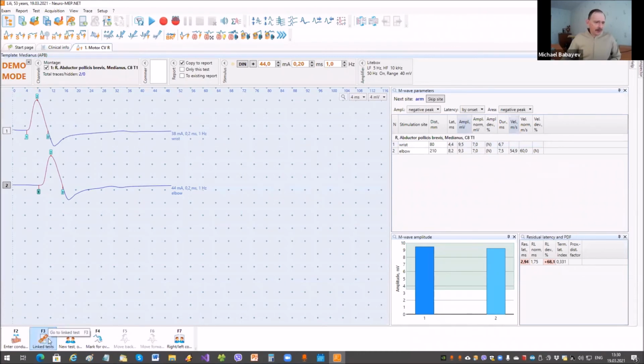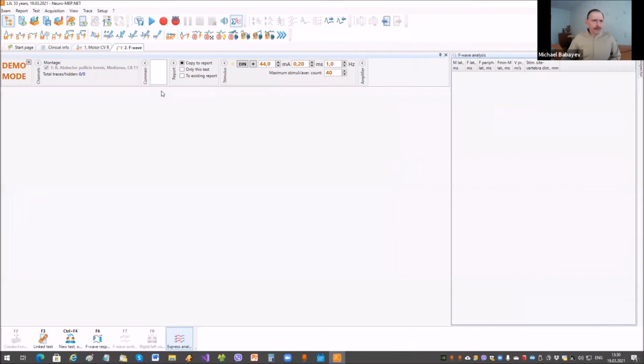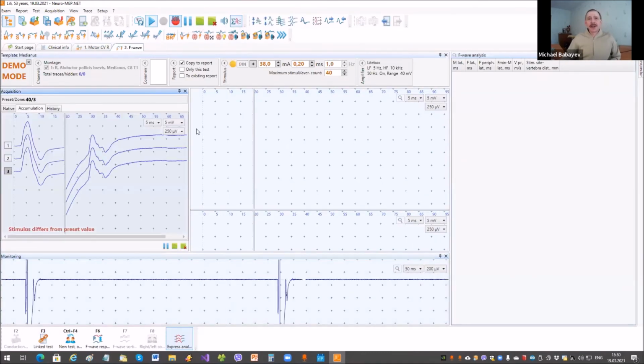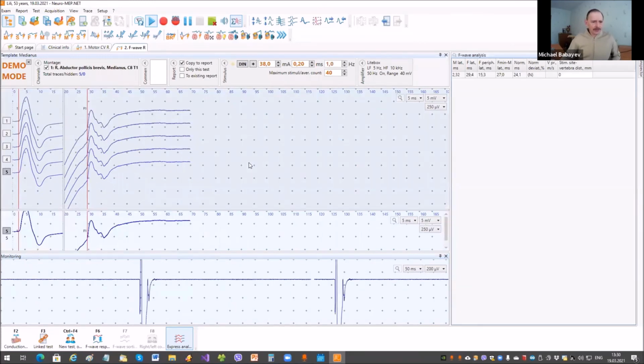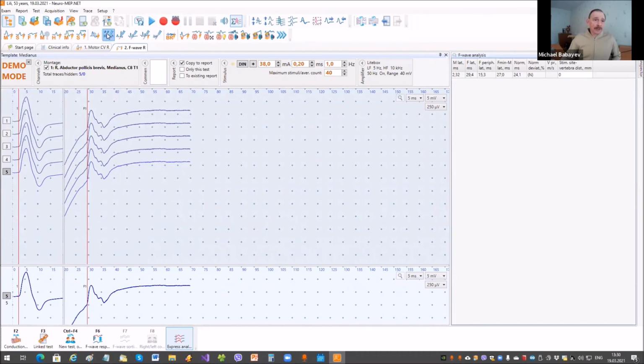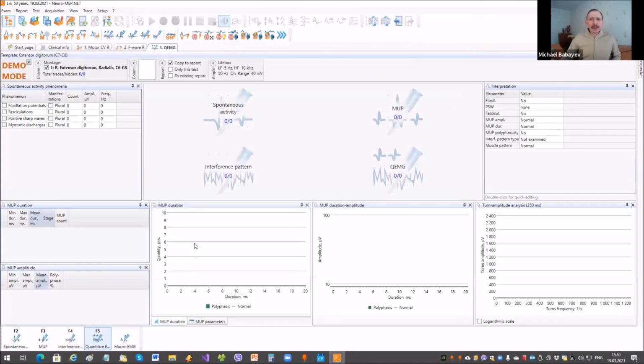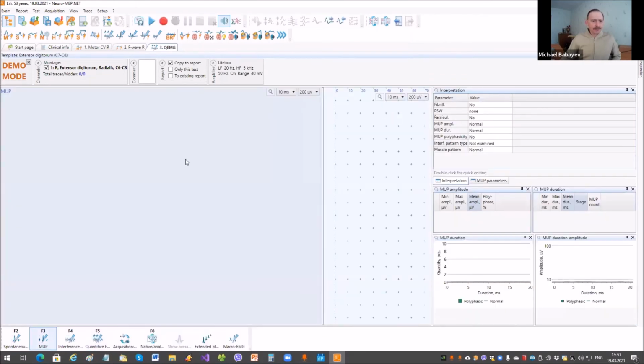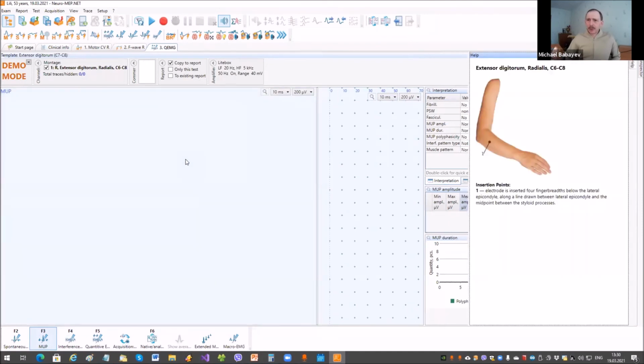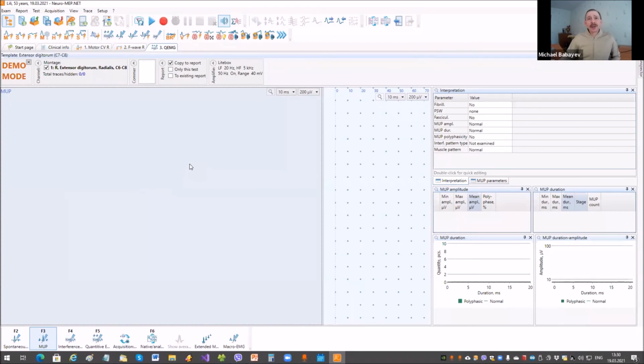Then we can go to another test, for example, go to F-wave, and start acquisition here. As you can see, it is very easy and fast. We can record data. Then, for example, we can go to quantitative EMG if we would like to use needle EMG and record motor unit potentials or interference pattern. And in our system, there is also a special help window showing where to put a needle. We have an automatic system. It does not use some triggers and other very complex tools that some other EMG machines have. You only need to put the electrode into the muscle and start acquisition.